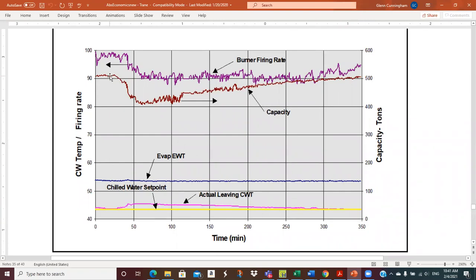Control system is here. So up here on the top, we have the burner firing rate. And then we have the capacity on the machine. We have the evaporator entering water temperature, that's coming back from the system, and the actual leaving chill water temperature, and then the yellow is the set point. So it looks like the set point's down here, I don't know, was that 44? Looks like it's probably about 44. And so we're rocking along, we're right about on set point.